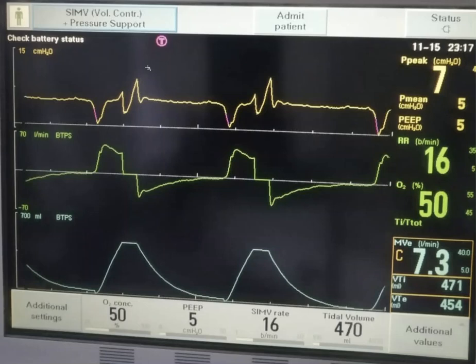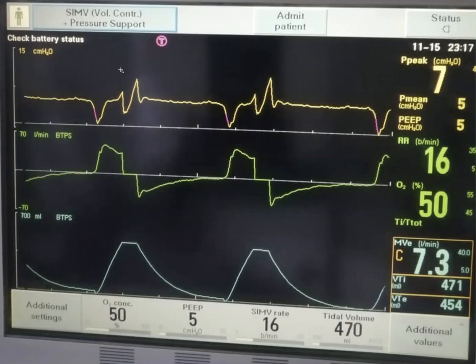Now, what's happening with the pressure here? This is volume control, and the aim is to deliver 470 ml of tidal volume. While the machine will utilize pressure to deliver that tidal volume, this pressure is dependent on three factors: resistance of the airway, compliance of the lungs and chest wall, and patient's efforts. So that pressure will go up and down based on these three factors. It's unlikely for resistance and compliance to change within the breath, so the variation in pressure within inspiration is related to patient's efforts.